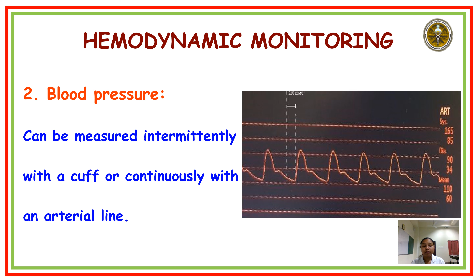In this picture, you can see the arterial waveforms. The measuring apparatus consists of an arterial cannula connected to a tubing containing continuous column of saline which conducts the pressure wave to the transducer. The arterial line is also connected to a flushing system consisting of a 500 ml bag of heparinized saline pressurized up to 300 mm of mercury via a flushing device. Second is the transducer. Transducer converts one form of energy to another. The transducer should be placed at the phlebostatic axis, that is fourth intercostal space mid-axillary line.